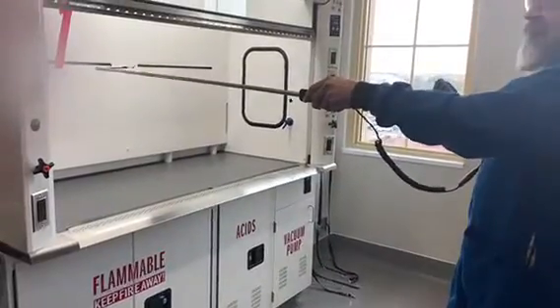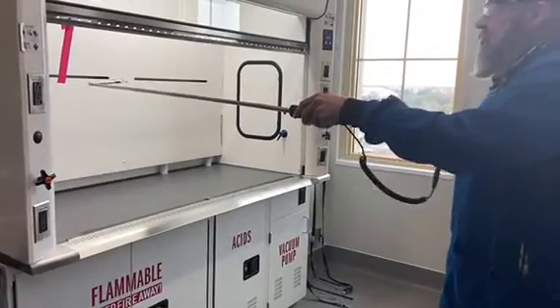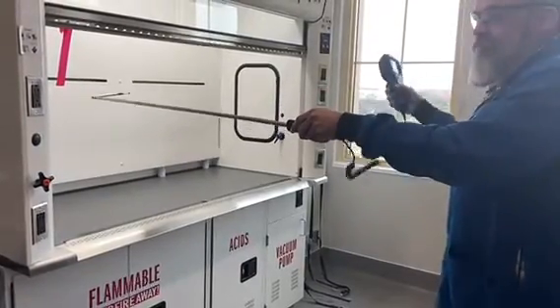So we're measuring in feet per minute — the air face velocity, the air going in. You pull down to a measure of your safety.